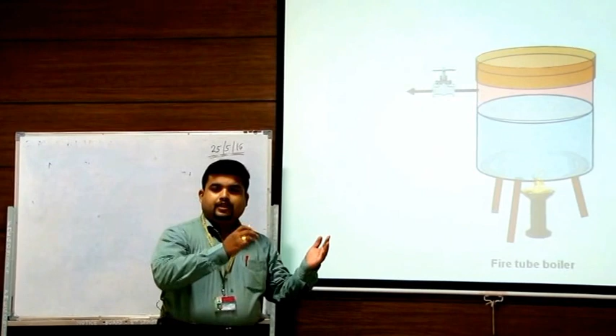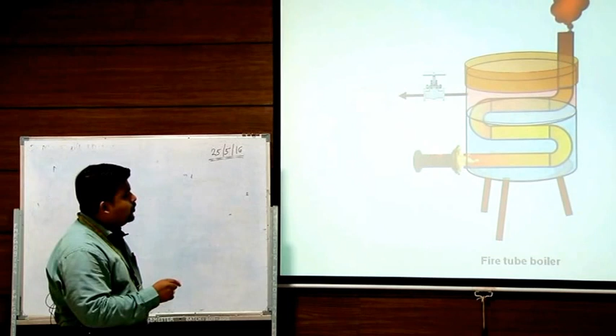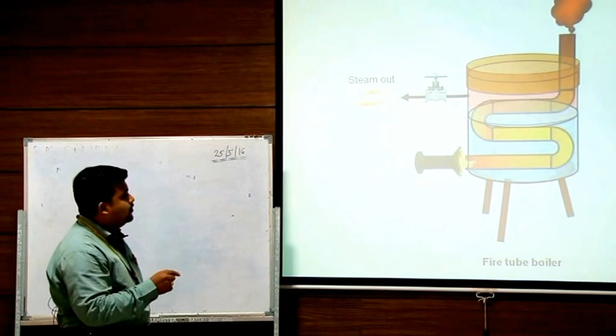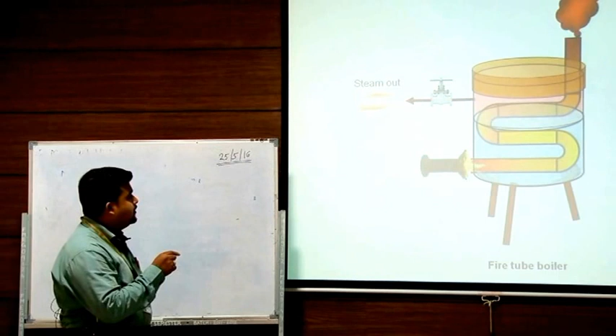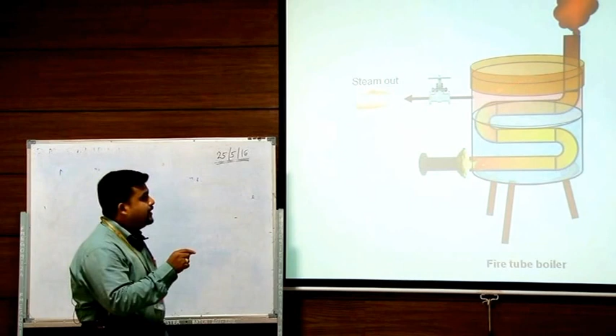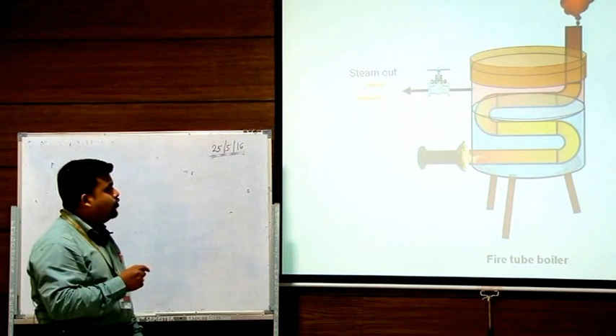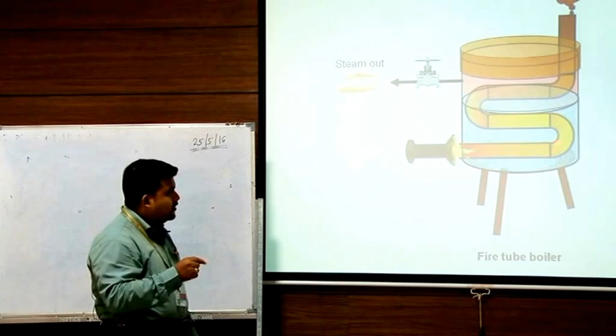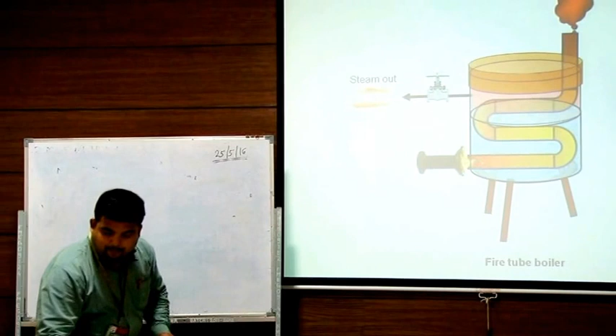Now second, as we discussed, is the fire tube boiler. Again we go back to our initial senses that yes, we have one container having water, having a lid, that is a boiler. But a fire tube boiler is something where the heat source is flowing through the tube as flue gases and the water is surrounded by that particular heating tube, and you are getting the steam output. Now in this case, the capacity of this lid, the capacity of this pressure vessel is something which has to be taken care of, because of which the produced steam has less pressure compared to the same capacity of the water tube boiler. So it also provides less output, because as you can see, the heat transfer area which is available for the fire tube boiler is less compared to the water tube boiler.